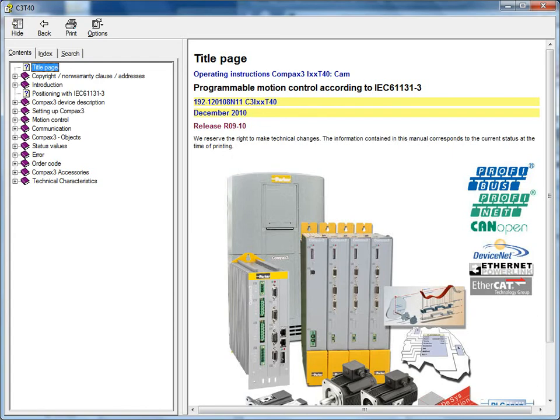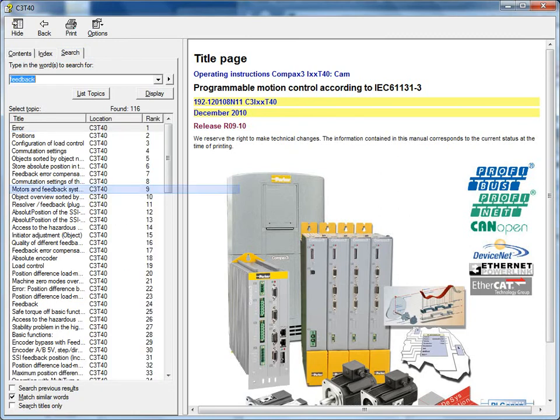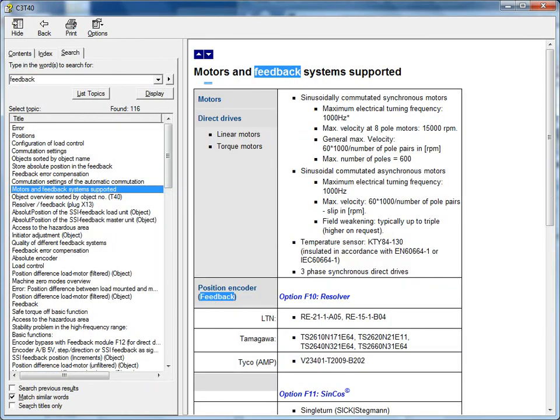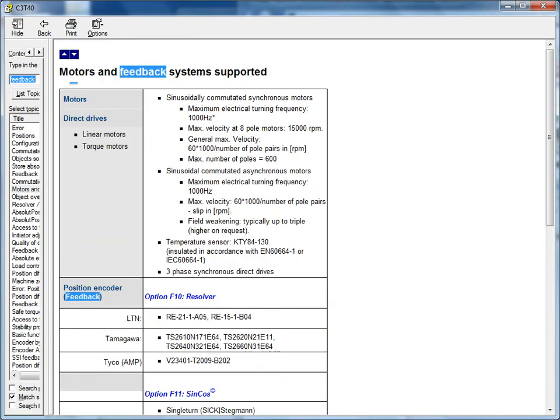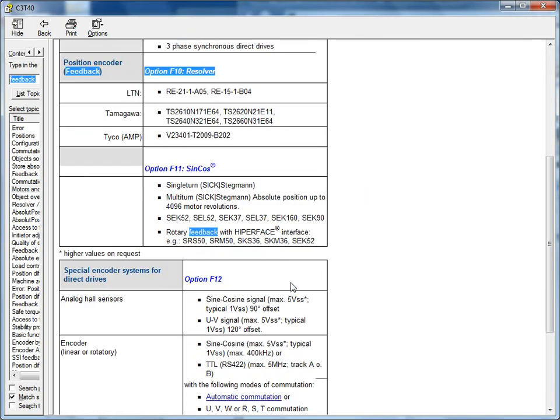If you go into the search tab and type feedback, and press enter, you'll see motors and feedback systems supported. If you double-click on this, you can see the different types of feedbacks that are compatible with the Compax 3. The resolver is used on the F10 option. The F11 supports the Stegmann SinCos Absolute Encoders.